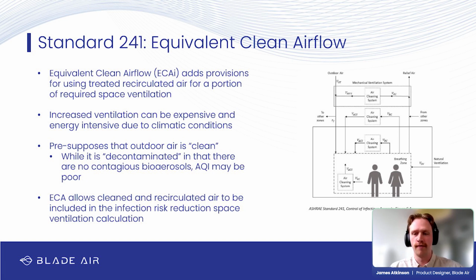Really, it's just to allow more variability for operators to meet these requirements, because the requirements for ventilation are extremely high under ASHRAE standard 241. And that's because obviously there's a huge risk, right? Bioaerosols, COVID-19, God forbid, some other new pandemic. There's a genuine risk to human health. So these standards are very, very stringent, which means they had to allow some wiggle room for people to meet it in other ways, because a lot of systems just frankly could not meet this amount of ventilation at all, even if they took the filters out and just dumped fresh air in.